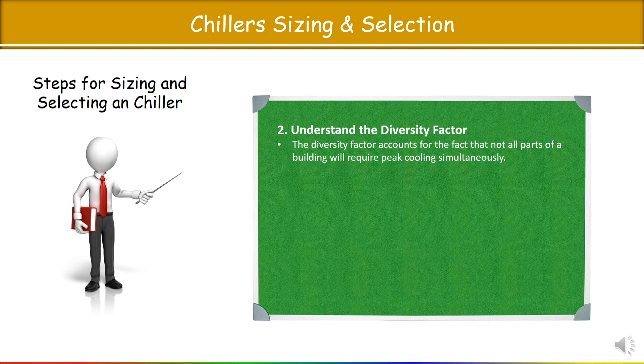The diversity factor accounts for the fact that not all parts of a building will require peak cooling simultaneously. If you have a high-rise building with different AHU/FCU units, we know that all of these AHU/FCU units are not 100% in working condition simultaneously. That is why diversity factor is very important — to save cost on equipment and energy consumption.